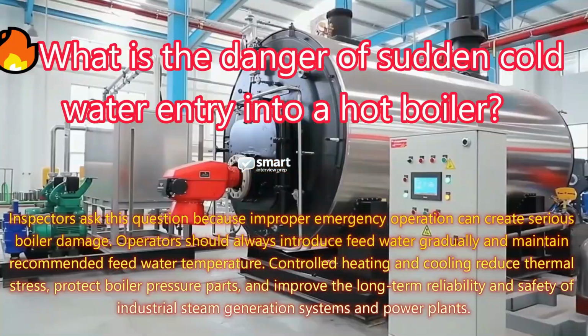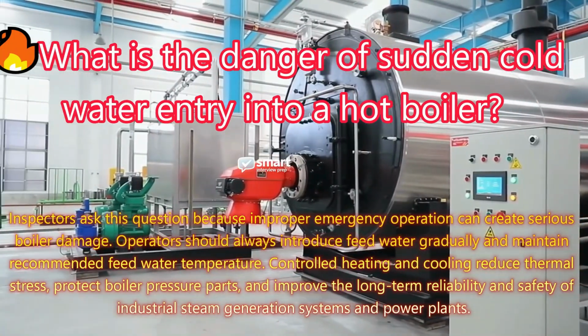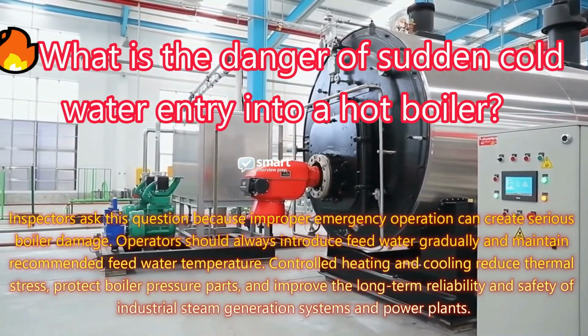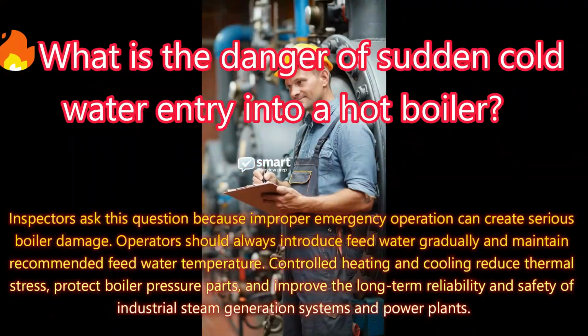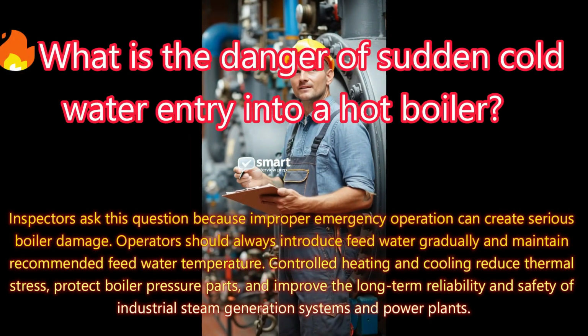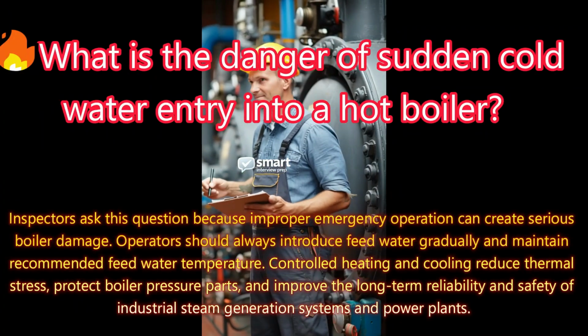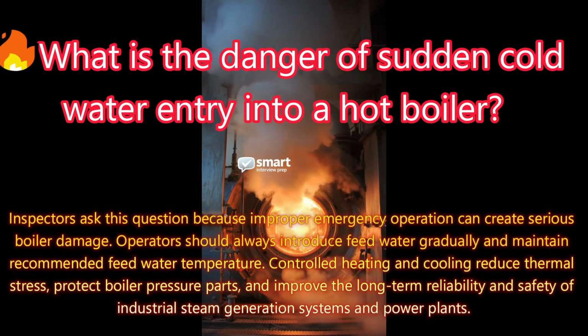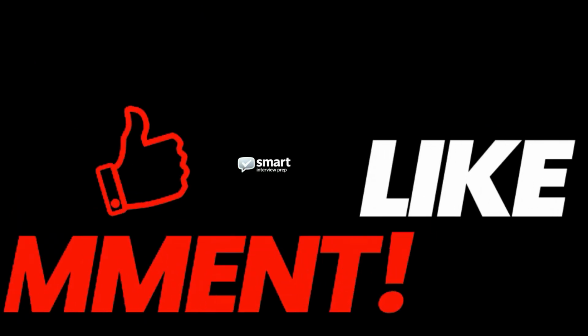Operators should always introduce feed water gradually and maintain recommended feed water temperature. Controlled heating and cooling reduce thermal stress, protect boiler pressure parts, and improve the long-term reliability and safety of industrial steam generation systems and power plants.